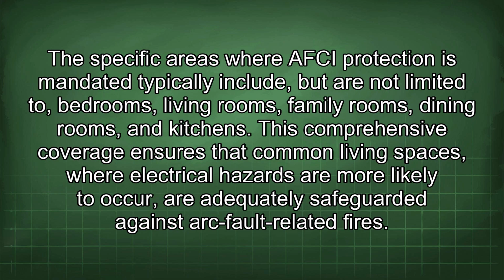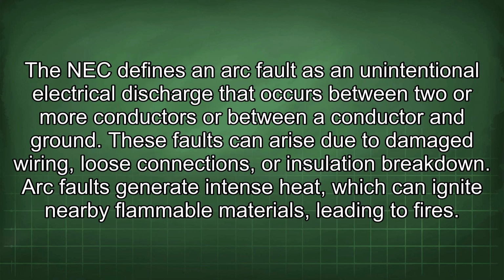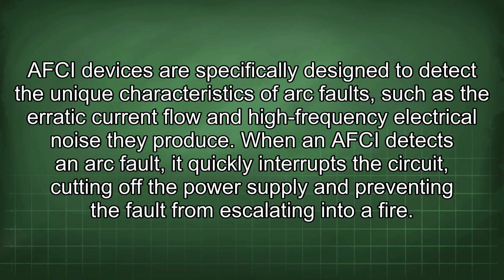arc fault-related fires. The NEC defines an arc fault as an unintentional electrical discharge that occurs between two or more conductors or between a conductor and ground. These faults can arise due to damaged wiring, loose connections, or insulation breakdown. Arc faults generate intense heat, which can ignite nearby flammable materials, leading to fires. AFCI devices are specifically designed to detect the unique characteristics of arc faults, such as the erratic current flow and high-frequency electrical noise they produce. When an AFCI detects an arc fault, it quickly interrupts the circuit, cutting off the power supply and preventing the fault from escalating into a fire.